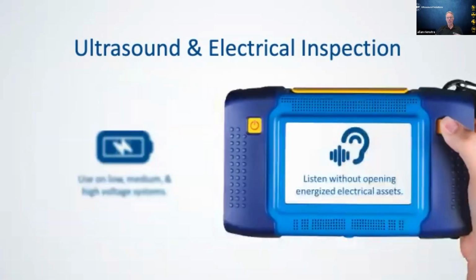Ultrasound also gives us the ability to listen to these assets without opening energized electrical assets in the case of electrical cabinets, motor circuit control panels, switchgear, etc. But if we're listening for substations, it allows us to listen on the safe side of the fence, or at least from a safe distance from the asset.